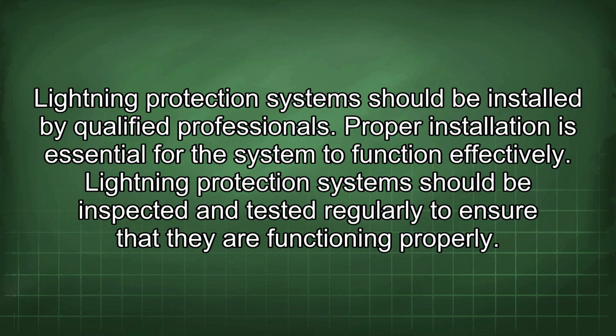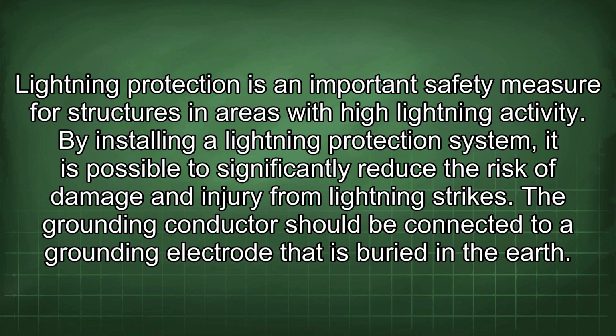Lightning protection systems should be installed by qualified professionals. Proper installation is essential for the system to function effectively. Lightning protection systems should be inspected and tested regularly to ensure that they are functioning properly. Lightning protection is an important safety measure for structures in areas with high lightning activity. By installing a lightning protection system, it is possible to significantly reduce the risk of damage and injury from lightning strikes. The grounding conductor should be connected to a grounding electrode that is buried in the earth.